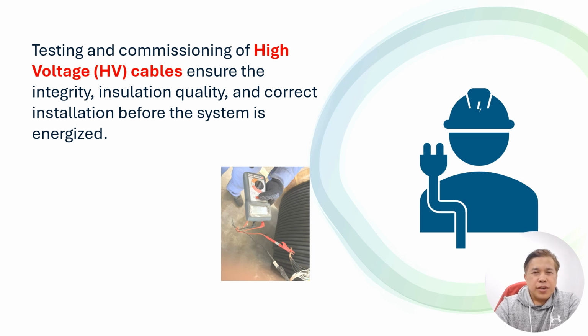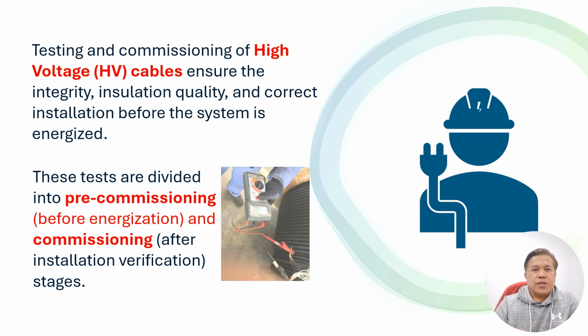So testing and commissioning of high voltage cables ensures integrity, insulation quality, and correct installation before the system is energized. This is how we start our activity during testing and commissioning. Of course, these tests are divided into pre-commissioning, before energization, and commissioning, after installation verification is done. So all the ITR checklist test sheets have been completed as part of the construction phase.